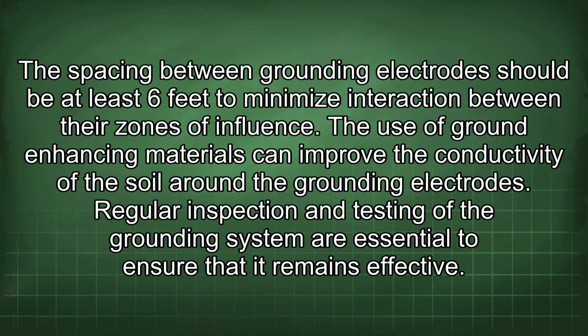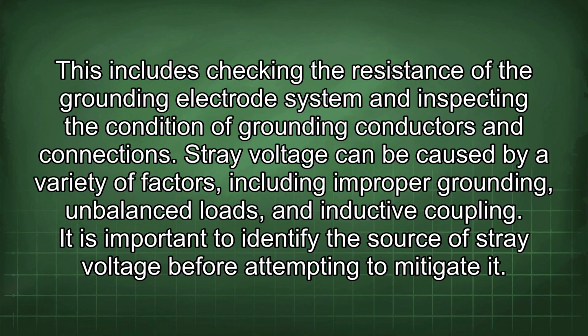Regular inspection and testing of the grounding system are essential to ensure that it remains effective. This includes checking the resistance of the grounding electrode system and inspecting the condition of grounding conductors and connections. Stray voltage can be caused by a variety of factors, including improper grounding, unbalanced loads, and inductive coupling. It is important to identify the source of stray voltage before attempting to mitigate it.